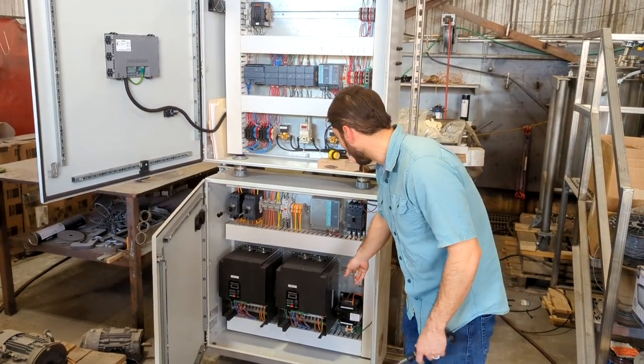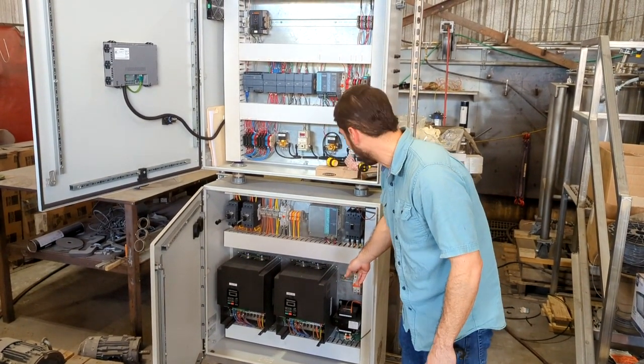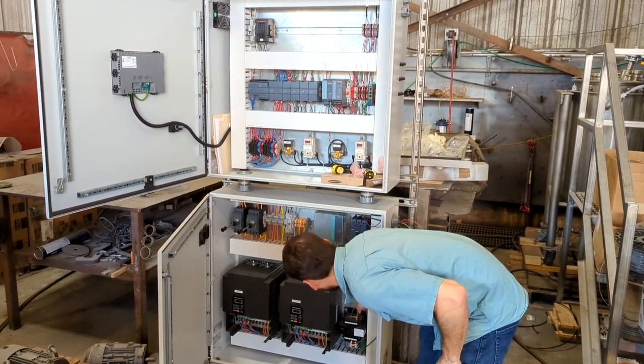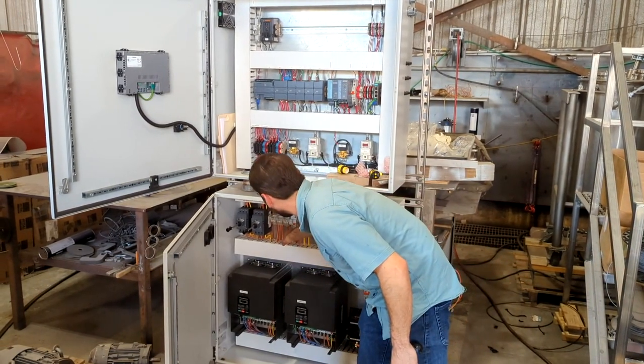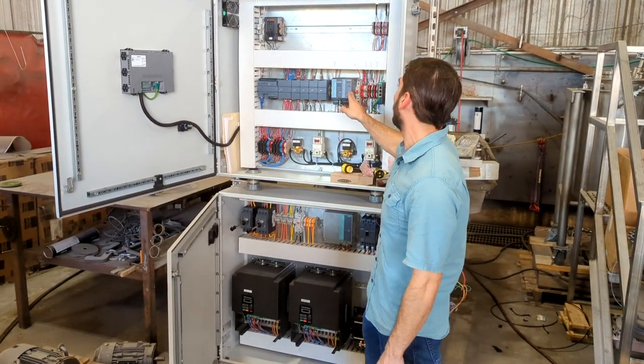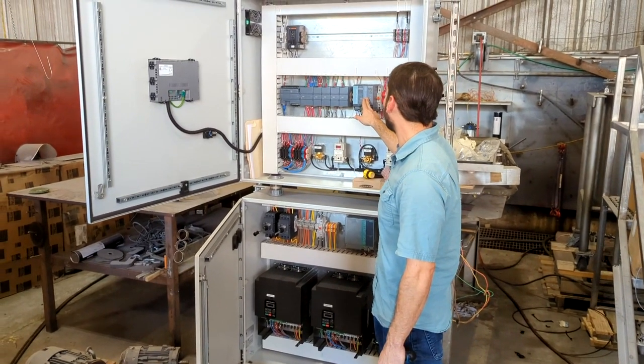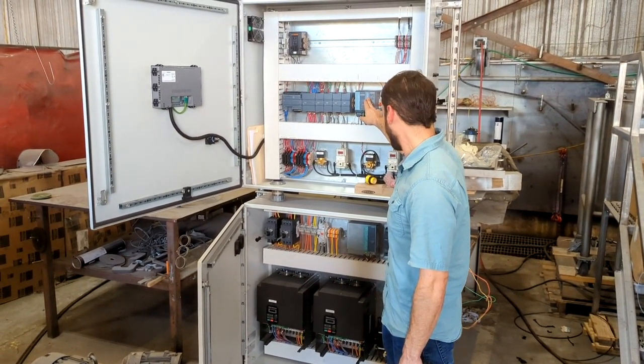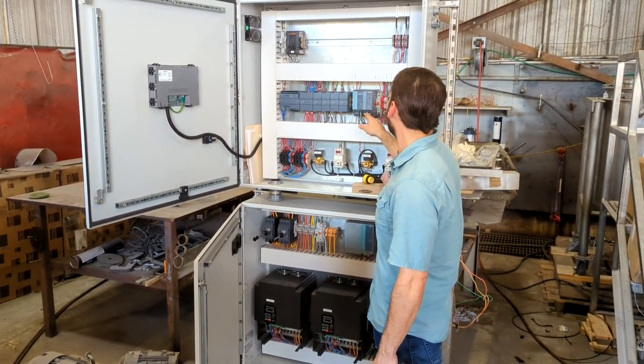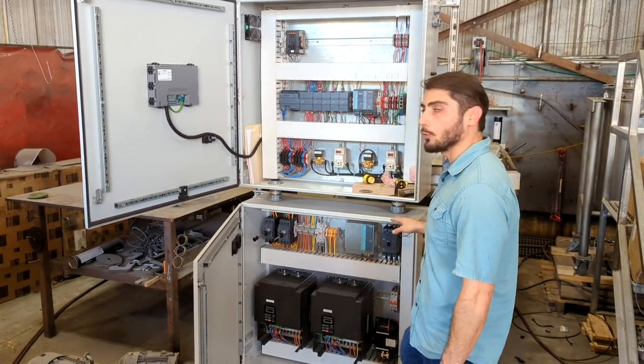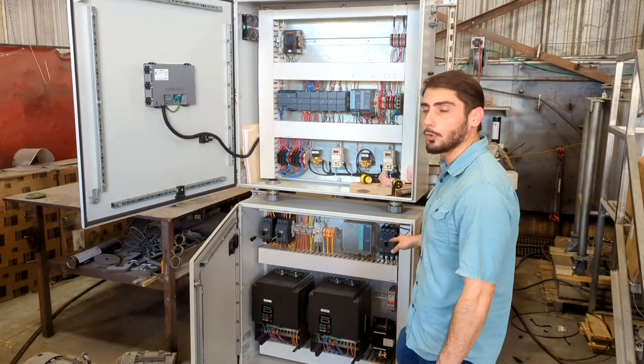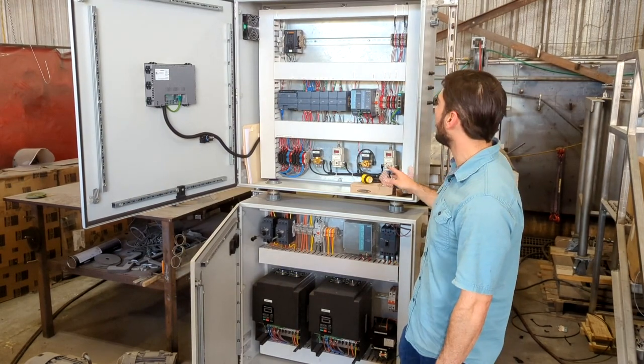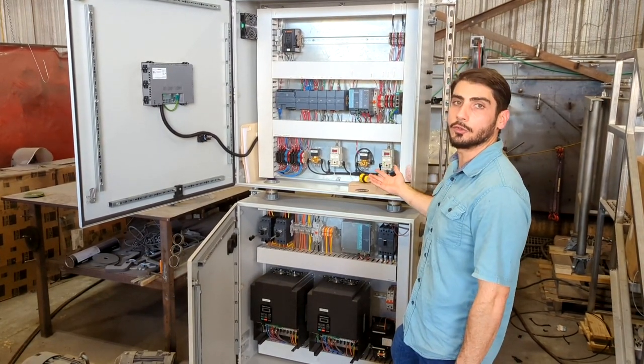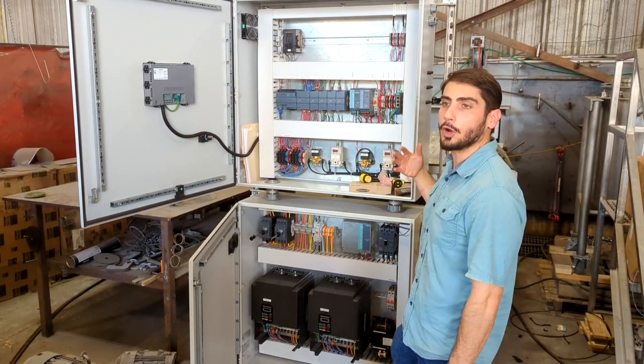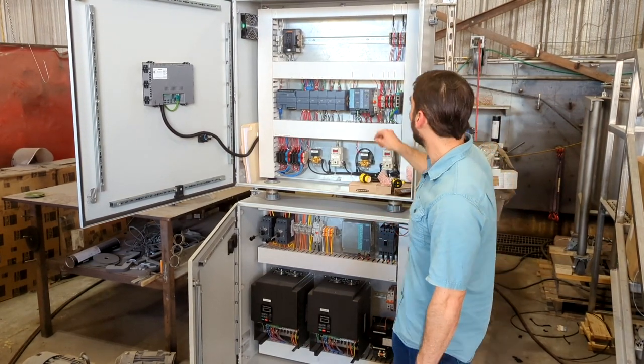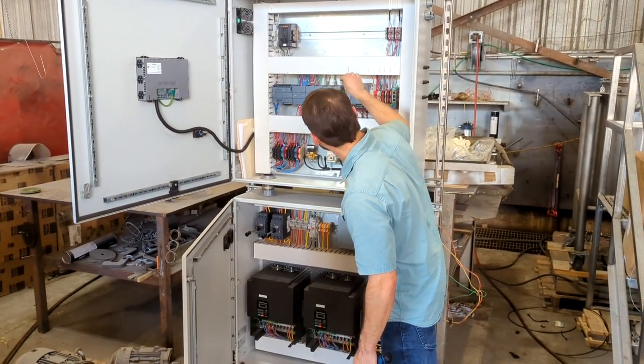We're running a 120 by 480 transformer at the bottom of this cabinet. We transform to 120, which goes up to our 24 volt power supplies. We're using a UPS to back up the PLC. So if you were to have an interrupted power supply, or if this main breaker would drop out, the PLC will continue to run, continue to collect the data, and let you know that there's a problem going on in the lower cabinet. Let's go ahead and power things up.